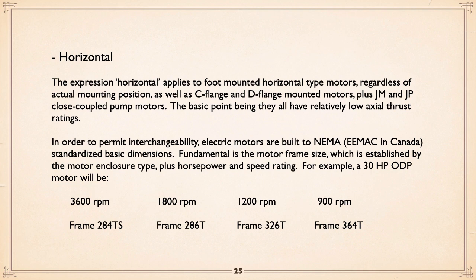It's an industry standard. But all horizontal motors, even if they're mounted vertically with flanges, have basically relatively low axial thrust ratings. They can't be used with a vertical turbine pump. And to permit interchangeability, electric motors are built to either NEMA, or EEMAC in Canada, standardized basic dimensions, so that you can interchange one motor with another. You've got whatever you're powering with a horizontal motor from one manufacturer, and that motor goes up in flames. You're looking around for basically a motor, same enclosure, same horsepower, same speed, and you get it from a different manufacturer. Because they're standardized, it will interchange. The shaft diameter, everything, they will interchange, and away you go.